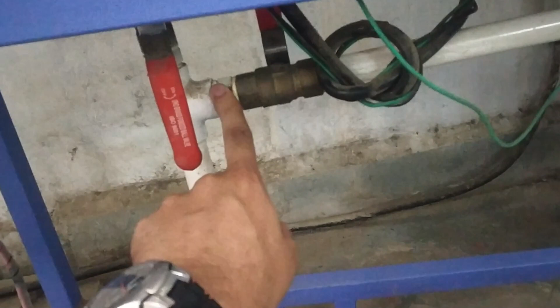So some part of the water can be sent back to the sump. If you operate this valve over here, we can regulate the water which is entering the cooling tower, and this valve also we can use to regulate it. Now if this is kept closed 100%, all the water coming from the sump will go to the cooling tower. But if this is opened a bit, there will be a bypass and some water will bypass back to the water sump. In this way we can manage the water flow rate going to the cooling tower.